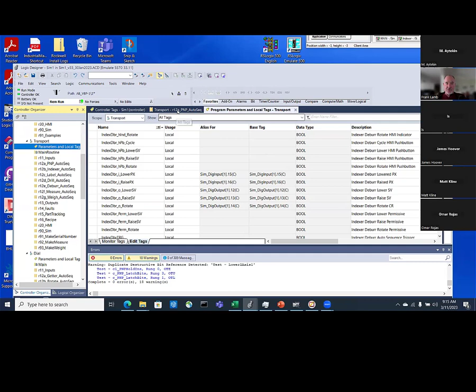You do the same for outputs. So any outputs I have in here, digital output 112. Okay, how does that operate? There is a simulation routine back here that detects that something's turned the output on. It turns on a moving part and responds when it hits the prox and cycles through the auto sequence. So this auto sequence, pretty straightforward. In step 10, it tells the Z-axis to lower. When the prox is made, it goes to step 20. You can kind of ignore some of this. I can explain this when we're done if you'd like.